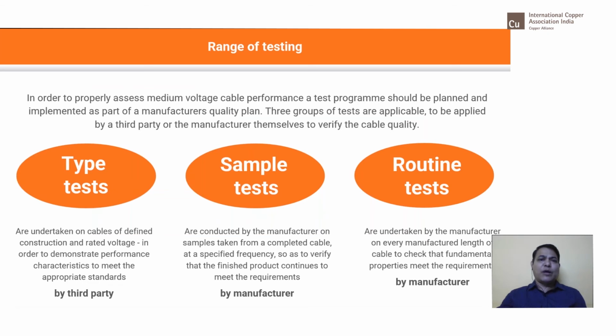So when it comes to testing of the medium voltage cable, there are three types of testing: type test, sample test, and routine test. So the type tests are a requirement of approval, as I said, to be assessed for a manufacturer, including all components, whole cable components, electrical test, mechanical test, all the tests to be done on individual compounds.